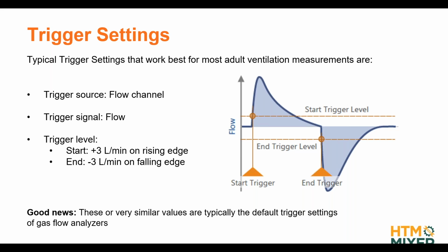Because the default trigger settings of your analyzer, of all the ones I've seen so far, are usually on the flow signal, for the reasons we just discussed. The start trigger is going to be on a low positive flow through the flow channel on the rising edge of the signal, and the stop trigger is going to be on a low negative number, like -3, for example, on a falling edge. Some you will see like 2 liters per minute, some 5. It doesn't really matter because this signal is so steep. Imagine if it's a little bit higher or lower, it doesn't really matter, right? So that's the good news.